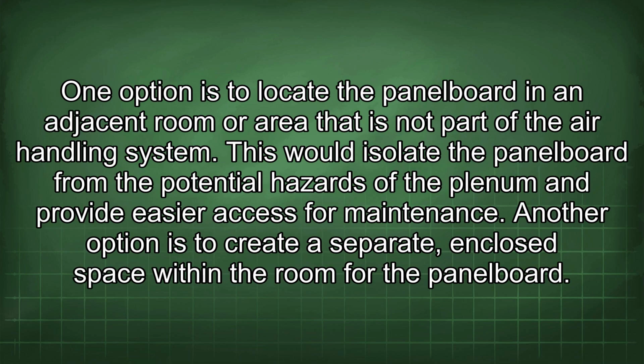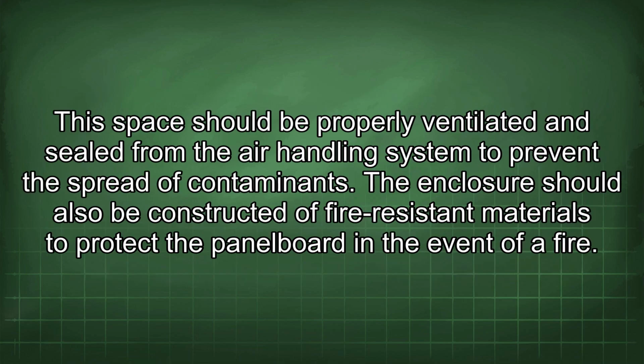One option is to locate the panelboard in an adjacent room or area that is not part of the air handling system. This would isolate the panelboard from the potential hazards of the plenum and provide easier access for maintenance. Another option is to create a separate, enclosed space within the room for the panelboard. This space should be properly ventilated and sealed from the air handling system to prevent the spread of contaminants. The enclosure should also be constructed of fire-resistant materials to protect the panelboard in the event of a fire.